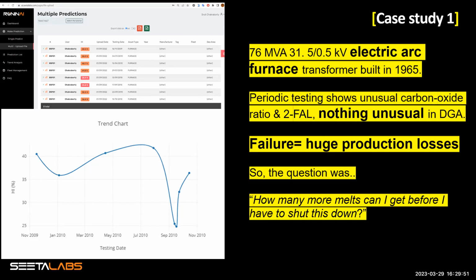So what you see here is a time series of health index over a certain period of time, about a year, of that particular transformer. And what we noticed is that the moisture kept on increasing. Although the degradation is not that much, the moisture kept on increasing. So every time, no matter how much filtration they are doing or how much degassing they are doing, the moisture is increasing. Definitely something is going on.